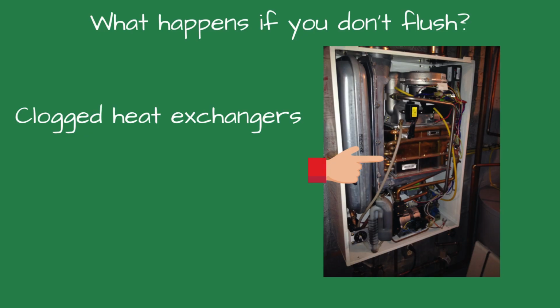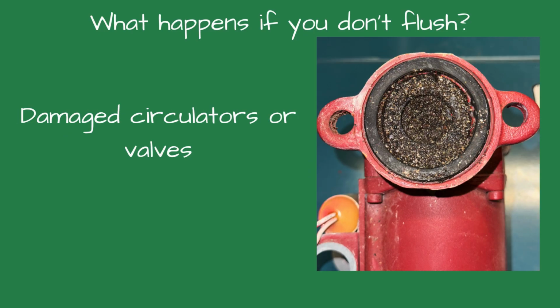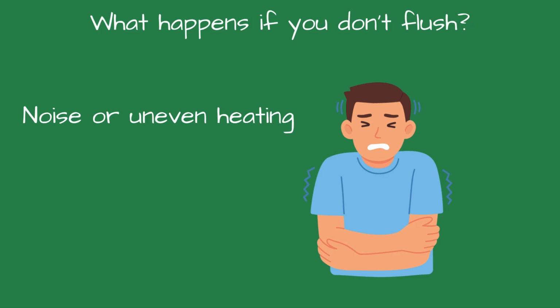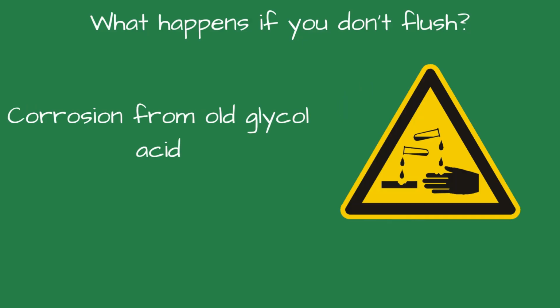You get clogged heat exchangers. Debris and scale can block narrow passages, causing overheating and nuisance shutdown. Damaged circulators and valves. Sludge grinds away at pump bearings and impellers, while grit can jam or stick zone valves and check valves. Noise and uneven heating. Scale and sludge create hotspots, leading to kettling noises, banging, and gurgling. Rooms may heat unevenly as circulation suffers. Premature corrosion from old glycol. Old glycol is one of the worst offenders. As glycol degrades, it produces acids that corrode piping, pump seals, and pit boiler materials. If inhibitors were not maintained, glycol can become a system-wide corrosive soup. This often results in leaks, rust-colored water, and even heat exchanger failure within a few years.